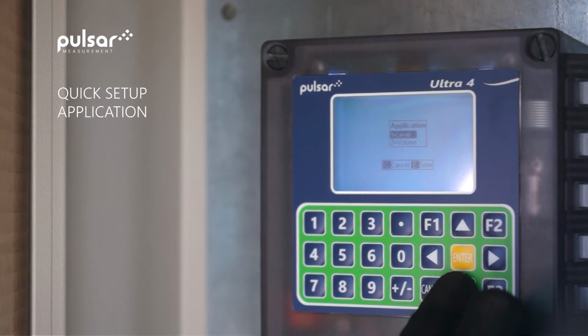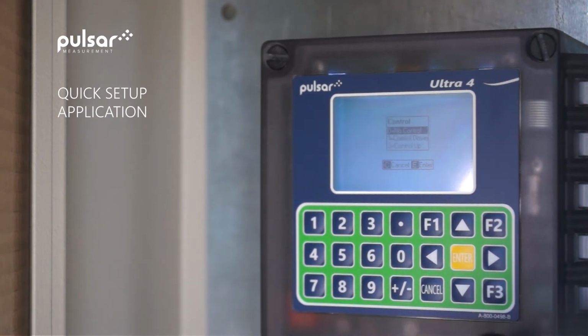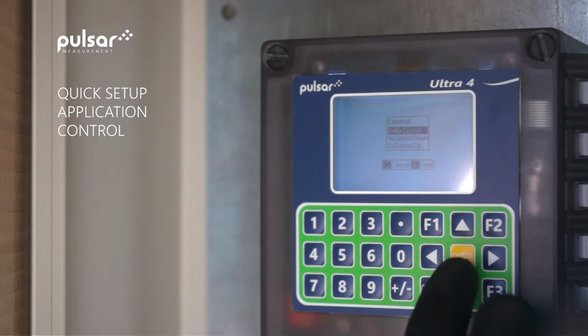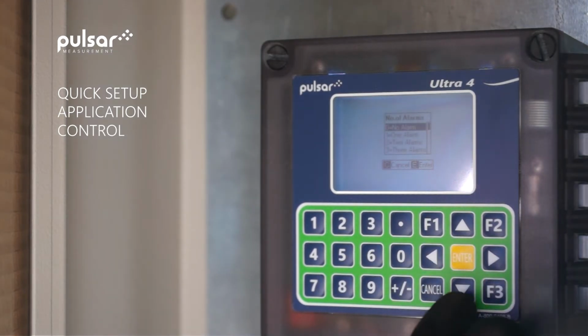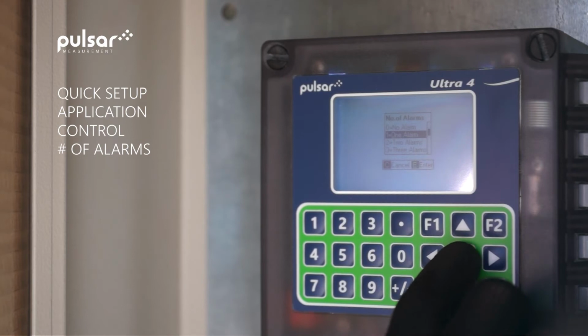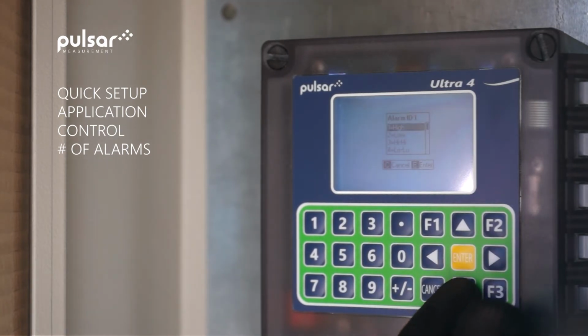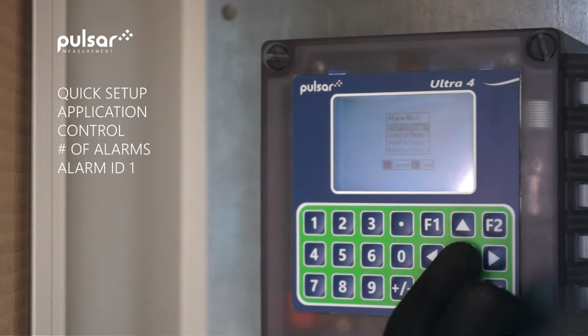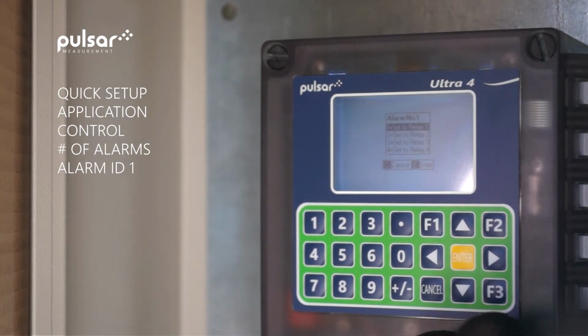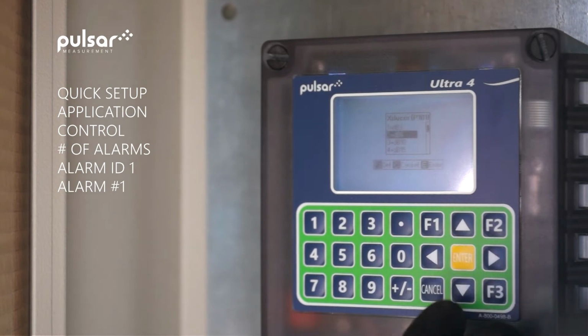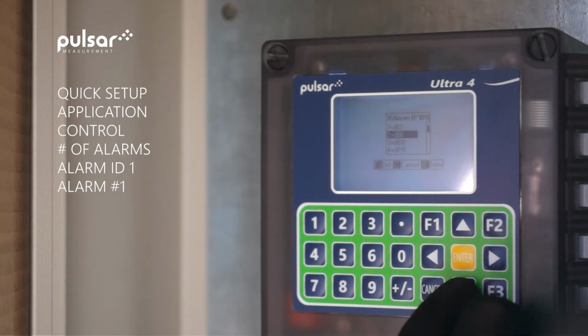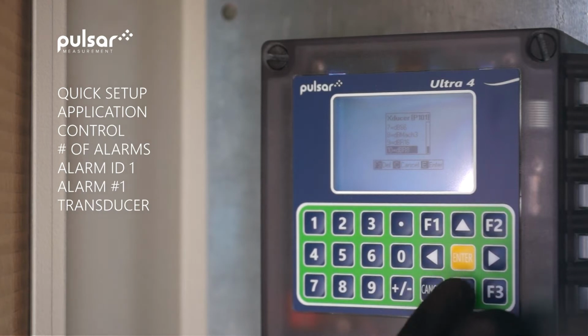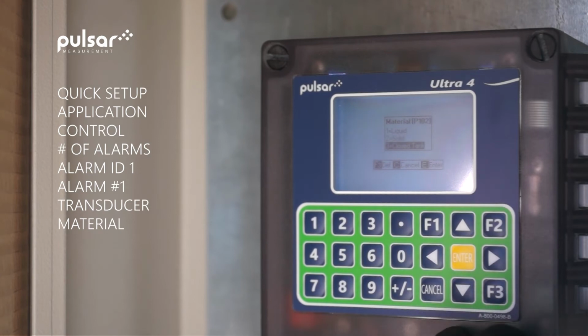We'll be using a volume measurement. We won't have any control relays. We'll have one alarm relay, and we'll assign that to a low identifier. The low alarm relay will be assigned to relay 1. The transducer we're using is the dBR 8. And it's a closed tank application.